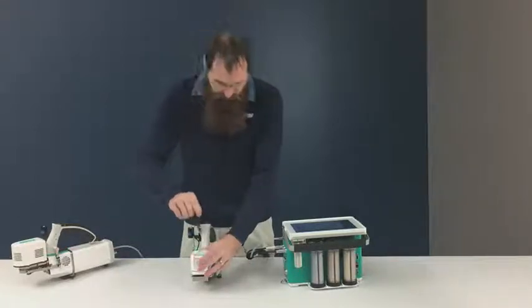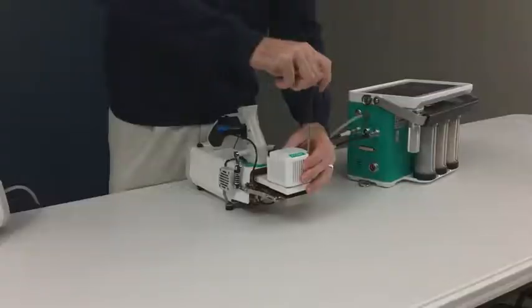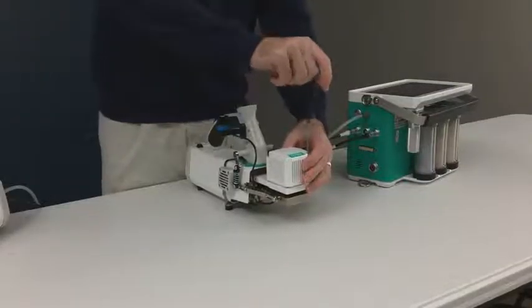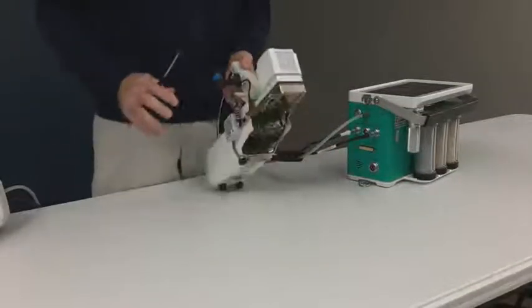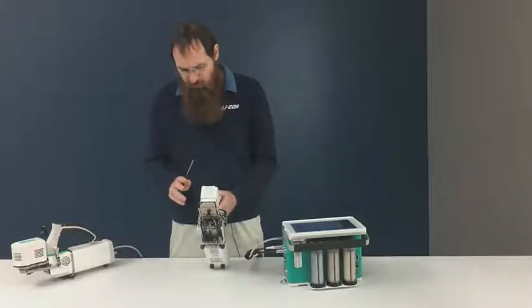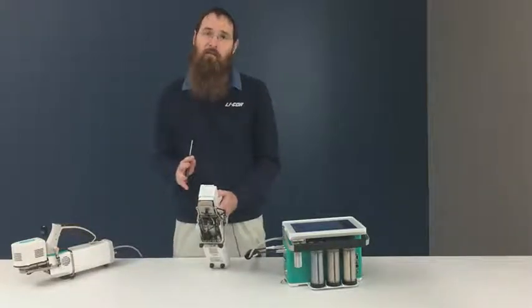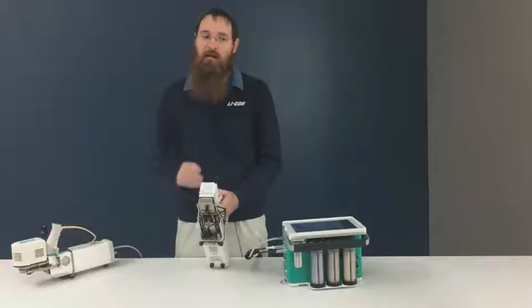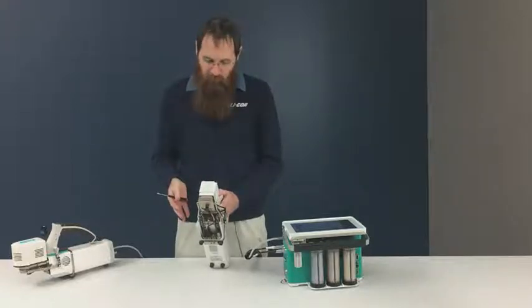Let me put this back on. The way the chambers come on and off the instrument, they're modular, so the chamber comes off as an entire assembly. There are no individual little pieces, and no little O-rings that can fall out.